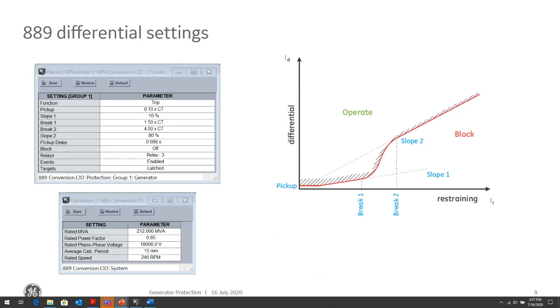The one thing that I always think about for a fault on the generator terminals is that when you initially strike that fault, even if it's a phase-to-phase or even a three-phase fault, you will produce a lot of fault current for a very short time. That's given by the subtransient reactance of the machine. But after a very short time, the voltage will collapse to the point that the current that you're providing to that fault is typically less than full load amps of the generator. So for that reason, you can't really use even a time overcurrent or an instantaneous overcurrent, because they likely wouldn't pick up, or if they did pick up, they'd drop out before they had time to expire in the case of a 51.